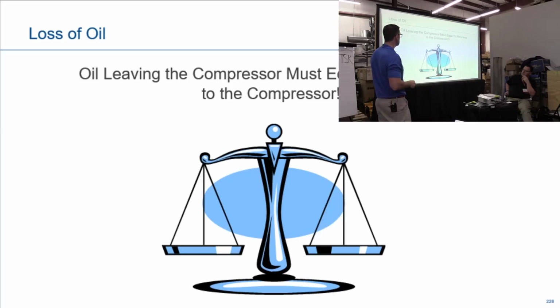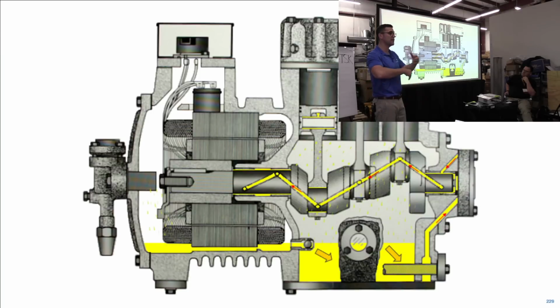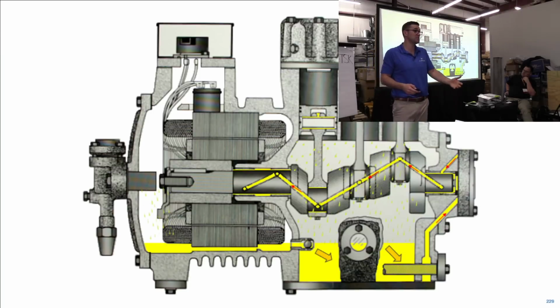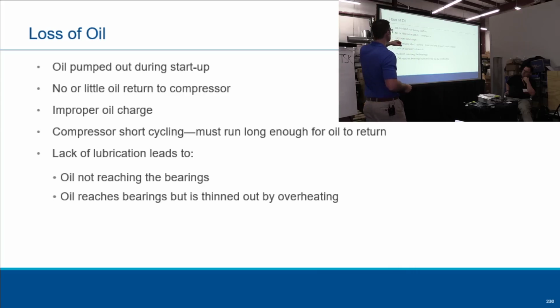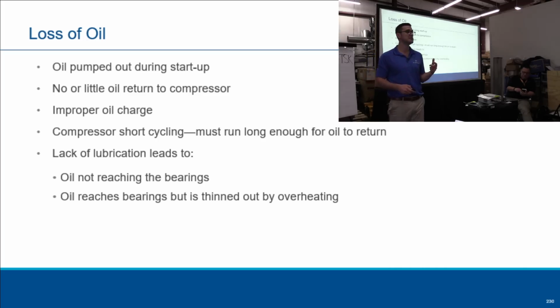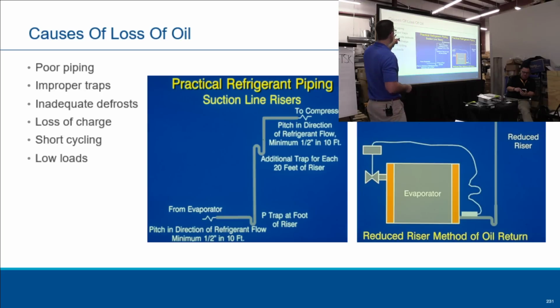Okay, loss of oil. Oil leaving the compressor must equal the oil returning to the compressor. So as that refrigerant is running, we're lubricating everything. Does this all make sense? Right, good. Oil pumped out during startup, little or no oil returning to the compressor, improper oil charge. Lack of lubrication leads to oil not reaching the bearings, and oil reaching the bearings but thinned out, like we talked about in overheat. Okay. Causes of loss of oil: poor piping, we talked about traps, short cycling, low loads.